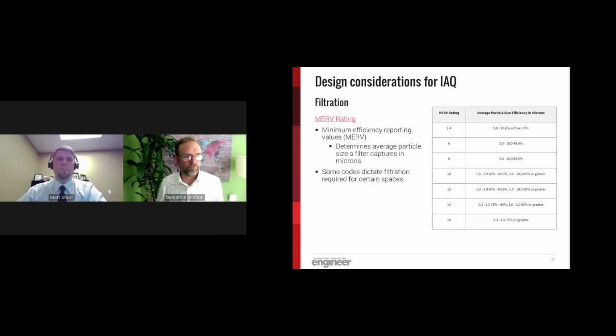Matt, I'll let you take filtration. Thank you. For healthy indoor air quality, filtration is one of the most important items we can consider in our designs. HVAC filters are rated by MERV ratings, which stands for Minimum Efficiency Reporting Values. The chart on the right indicates a filter's MERV rating and its associated average particle size efficiency in microns. These are some of the items in the codes we discussed earlier, and it's important to refer to them as they're specific to the facility you may be designing, as some have specific requirements for filter MERV ratings that serve a particular space.